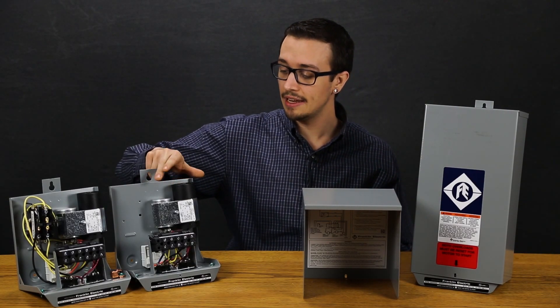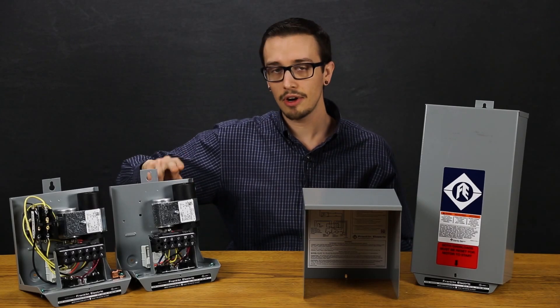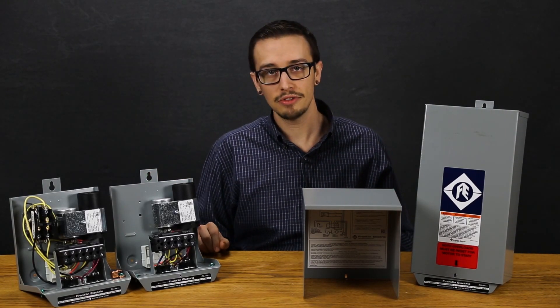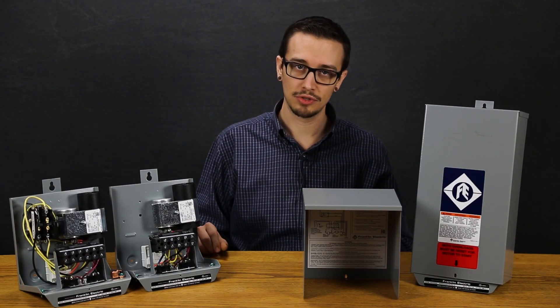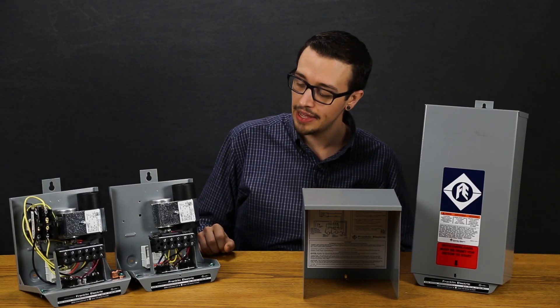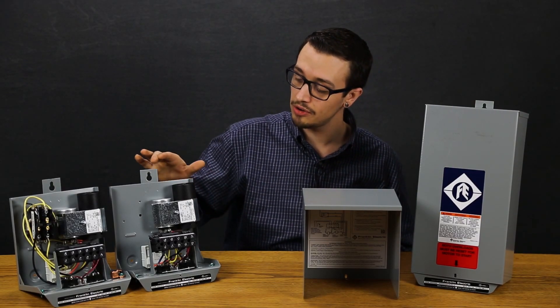Equipped with a start and a run capacitor — the start capacitor gives the motor a jolt to get it spinning, and the run capacitor is going to keep the motor running after the initial startup. There's a small white relay in the back of the control box that switches between the start and the run capacitor during motor startup.